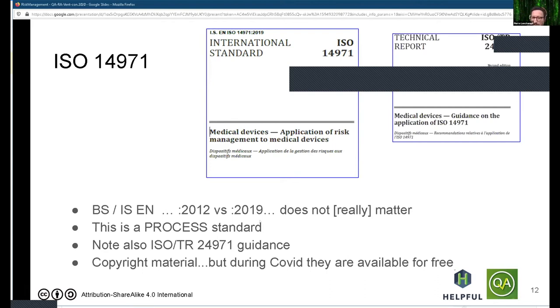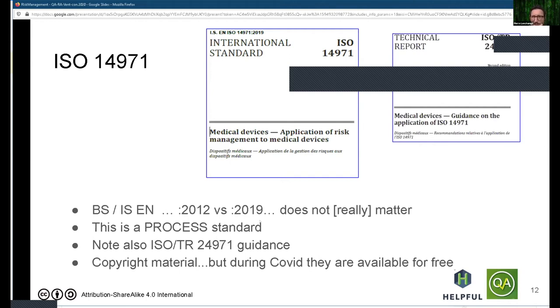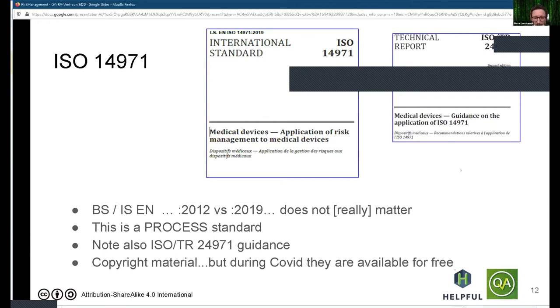That's not a product standard — it's a standard that explains how to do the process of risk management. There's also a great document, Technical Report 24971, which is really guidance that gives a lot of examples and explanation on how to implement the standard itself. These are copyrighted materials. In normal times you'd have to pay for the standards — a couple hundred dollars. During COVID, you can get them for free from various sources. I couldn't find the link when preparing my slides, but you can join me on Slack and I can help you find it.